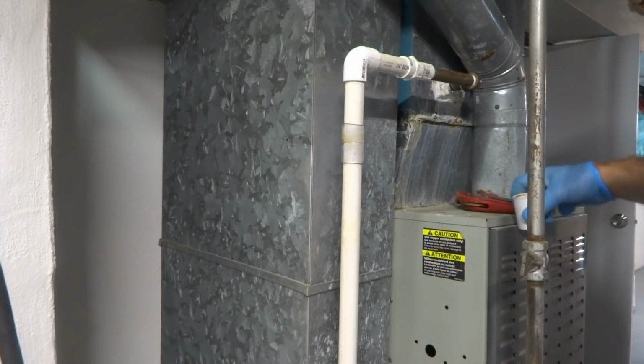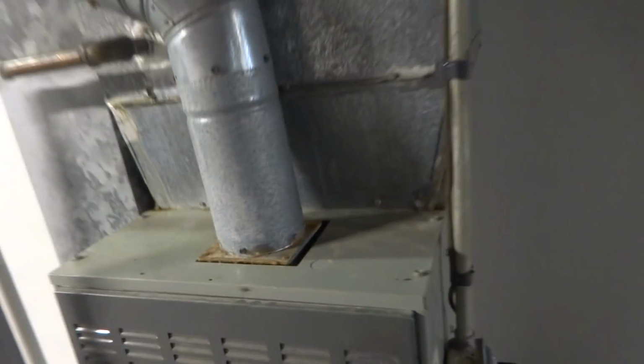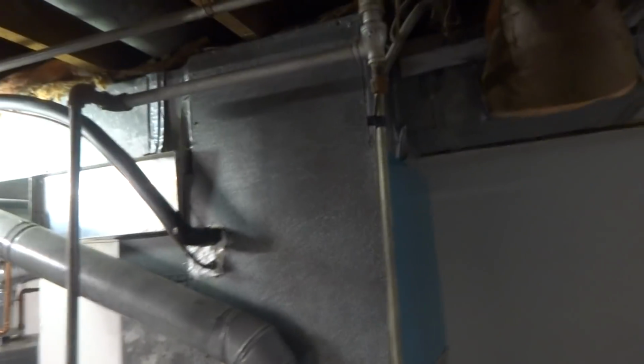Alright, we'll check it outside. It's a little Trane unit, a little 17-inch wide. So could always go with another little 2-tonner on top of that or something, and a little house. That's off. I don't know what that 30 amps is for. That's gonna be the dryer. AC's 10, 12, so it's 20. It's gotta be a 2-ton AC. We'll check it.